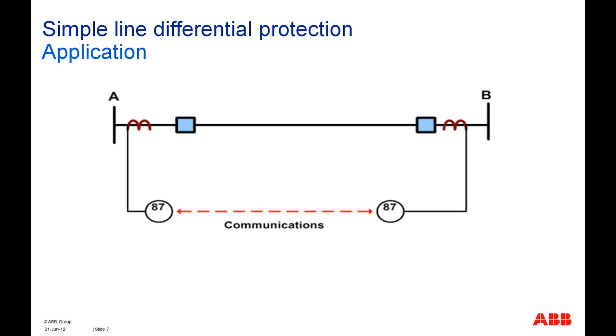So this is the basic idea of line differential protection. You have station A and station B, and between them you have a transmission line. You have two breakers, one breaker on the substation A side and another on the substation B side, with CTs connected on each side. A line differential protection box is connected to the CT at station A, and another box to the CT on the station B side. These two relays talk through a certain communication medium to exchange information, the analog and sometimes the digital, binary data. So that's the basic idea of line differential protection.